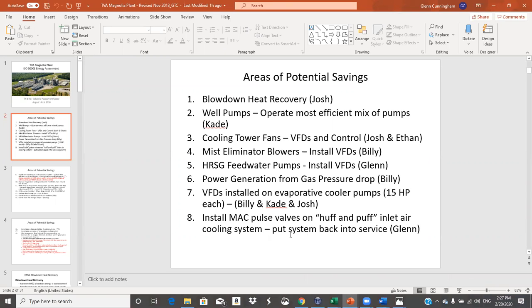All right, so this was pretty interesting. This got to be a big bone of contention. So those inlet filters, you saw on that diagram, the air comes in and goes right to the filter. Well, the filters were designed with a cleaning system called a huff and puff cleaning system. It would take compressed air out of one of the stages of the compressor, and every so often, through nozzles, it would blow back at, I don't know, say 50, 100 PSI to clean those inlet filters. And it was set up so that there's an avenue for that crud to get out and not just be re-entrained on the filter. I say, well, that seems like a really good idea.